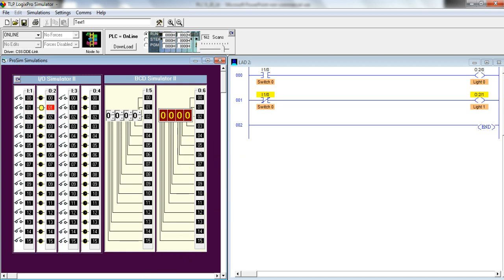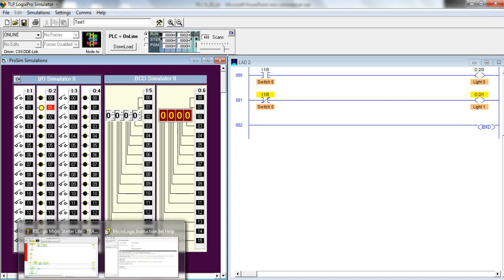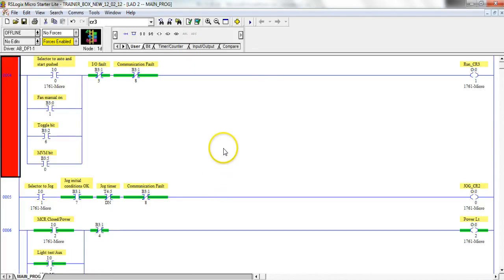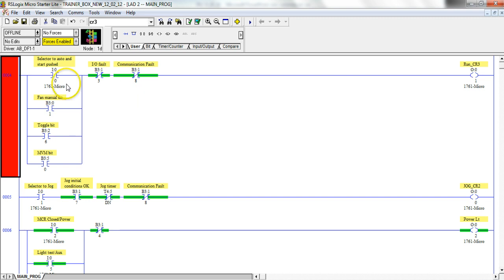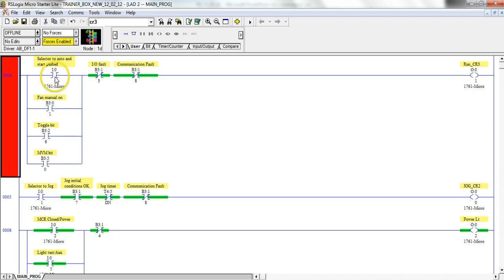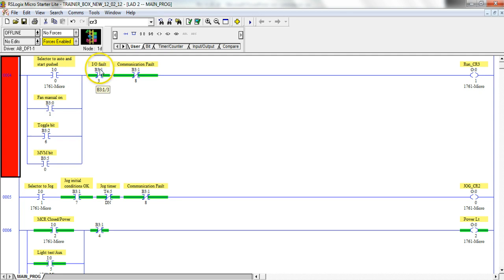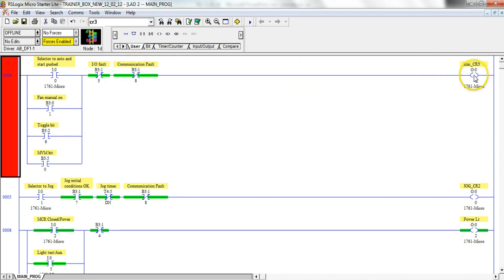If you look at a live Logix 500 program with a snapshot of this program, this is some of the code that I use in my class. So here's all the ifs, right? If the selector is to auto and start push, this is an actual input to the PLC. If we have that input, and if not a fault with the IO, and if not a communication fault, then we'll turn this output on.